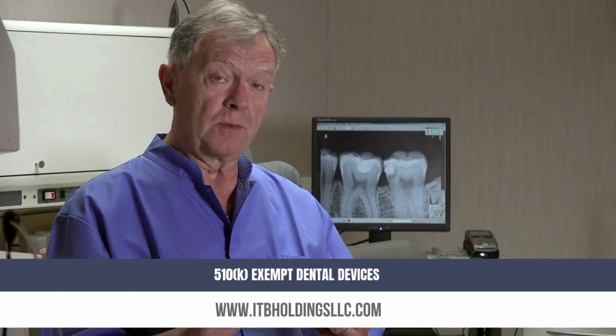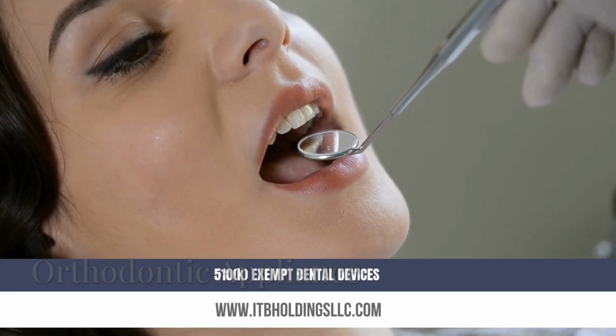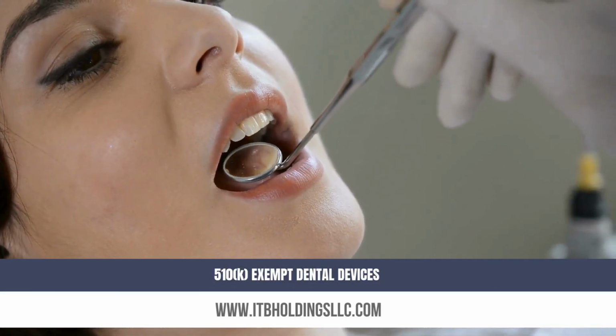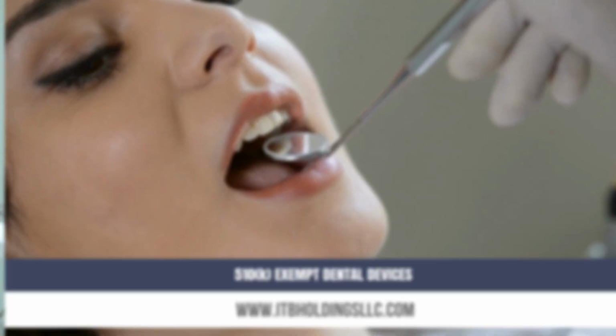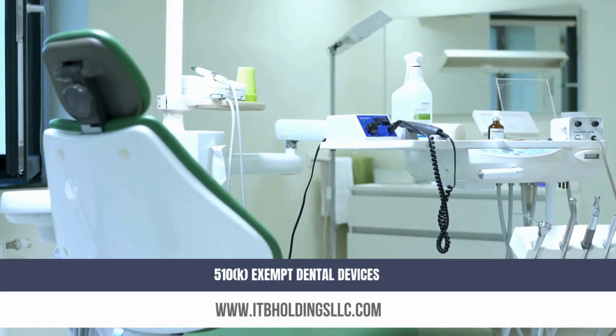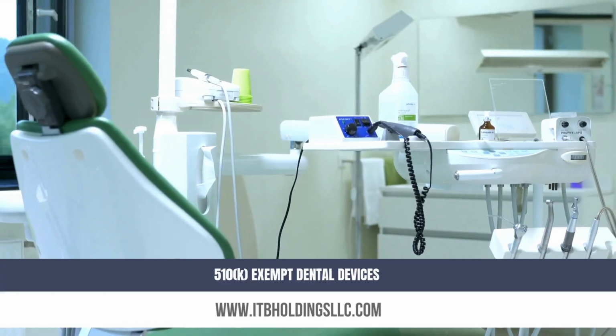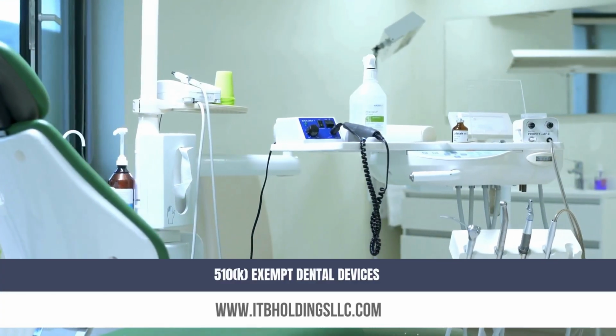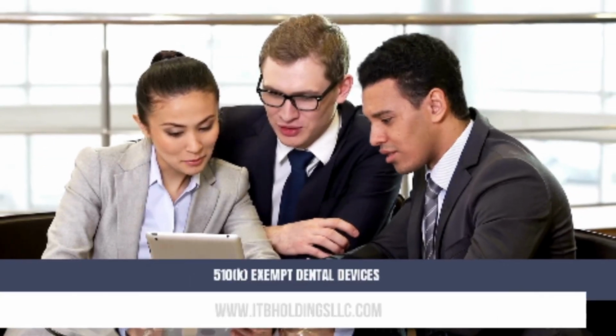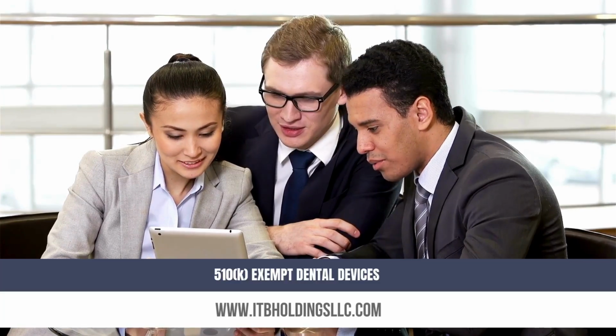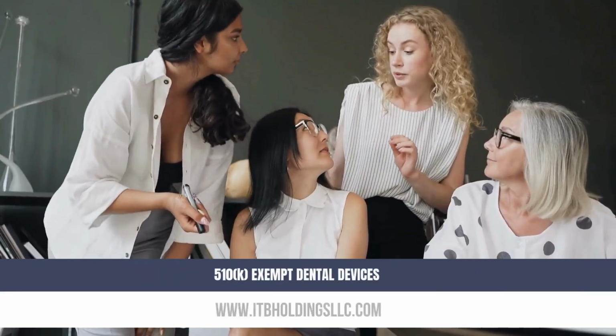Dental Injecting Needle, reprocessed dental needle, product code NMW, requires 510K clearance. Dental needle, product code DZM, is exempt from 510K. Orthodontic Appliance and Accessories, reprocessed orthodontic metal bracket, product code NQS, requires 510K clearance. Product codes ECI, DYO, ECM, EJF, ECN, DYJ, ECO, DZD, DZC are exempt from 510K. Here is the list of 510K exempt dental medical devices.